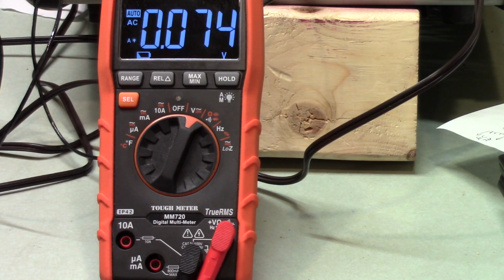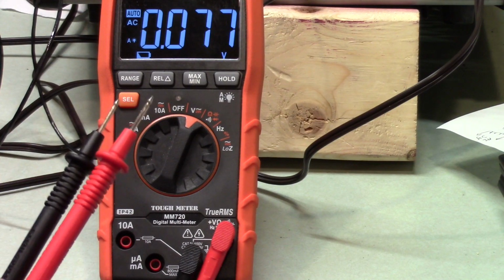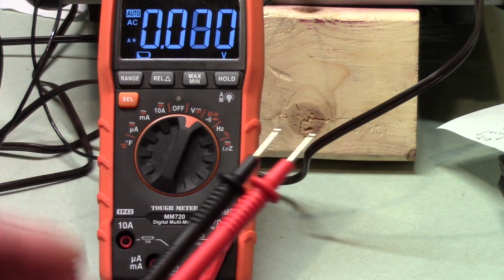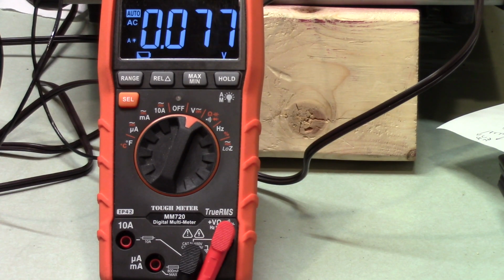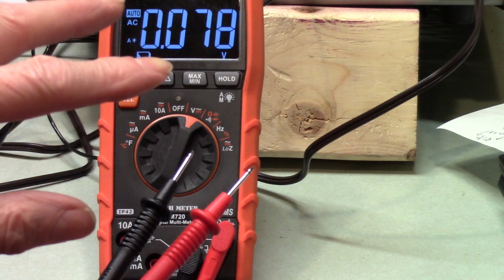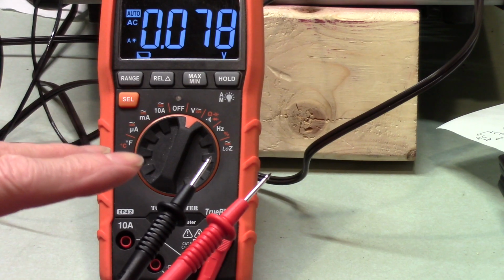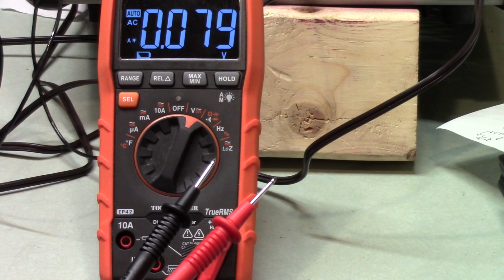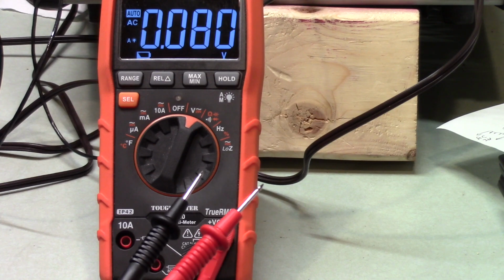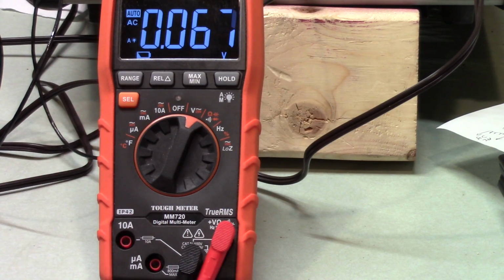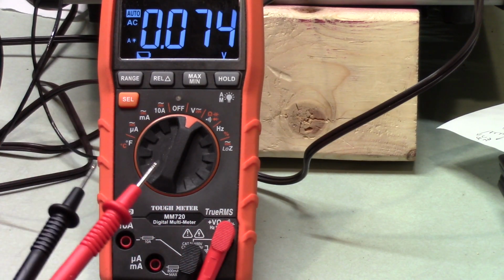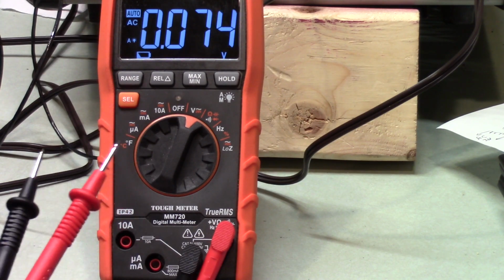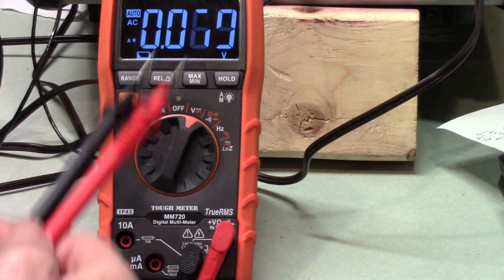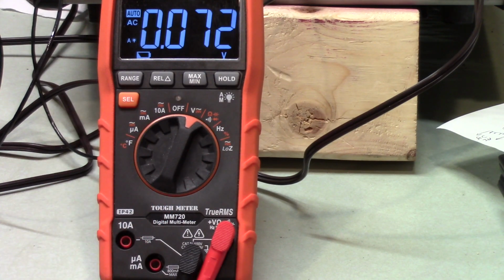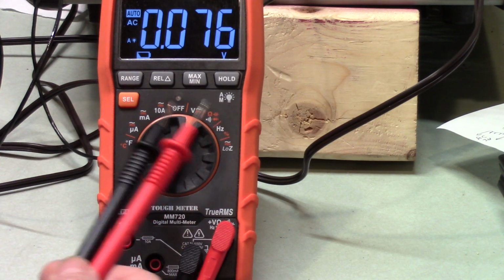That means that if you have a high resistance connection, say 500 ohms, so you're trying to test a dryer, you test at the outlet and you get 240 volts. You test at the appliance and you got 240 volts using this setting. You may have a high resistance in one of the wires and you'll never find it using this, because this doesn't really draw any current to speak of.